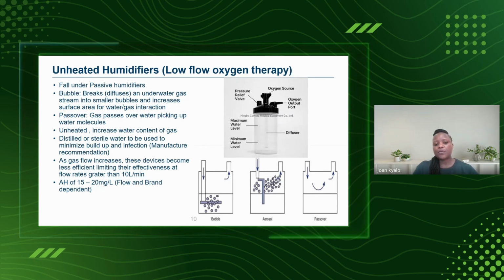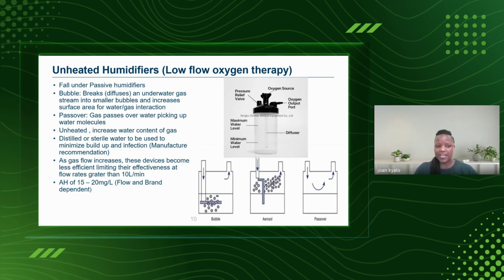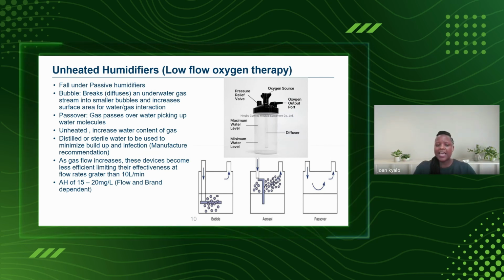So this humidifier, what happens is we give oxygen through here. It goes down. You have what we call a diffuser, and its job is really to break down the bubbles, so that you can increase the surface area for it to interact with the water in the bubbler. And what then happens? That gas, as it leaves to go to the patient, is carrying some level of humidity. Now, the level of humidity this particular sort of humidifier can give us can only be 15 to 20 milligrams.